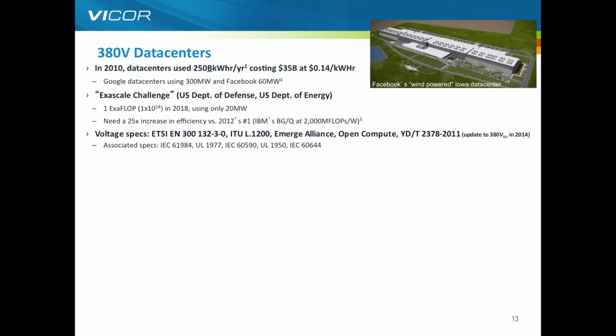In association with those specifications, we also have groups like the eMerge Alliance and the Open Compute group. Open Compute, if you're not familiar, is a group of people largely driven by the Facebook team, looking at ways to have efficient and also very cost-effective racks for generally lower power processing. The spec, as originally written, was up to 14.2 kilowatts in a 19-inch rack. That is now being rewritten with an additional 380-volt DC input to that specification. So that kind of open compute project is also having a high voltage DC input.